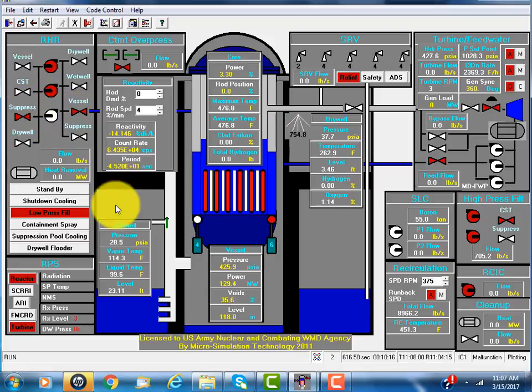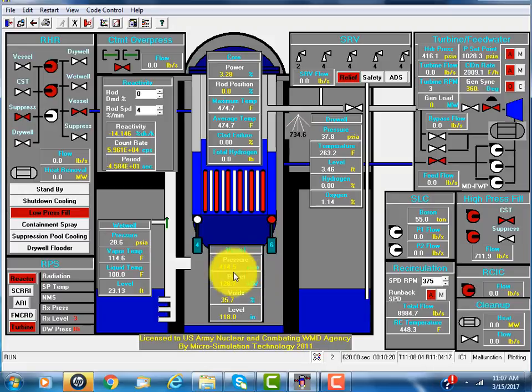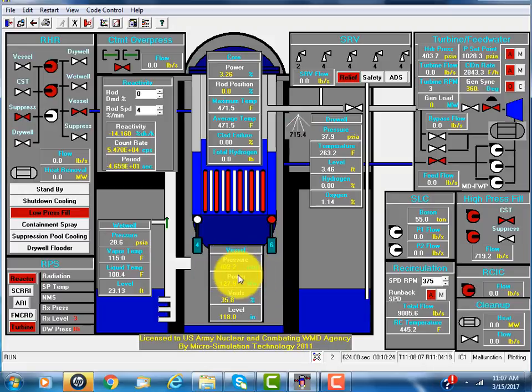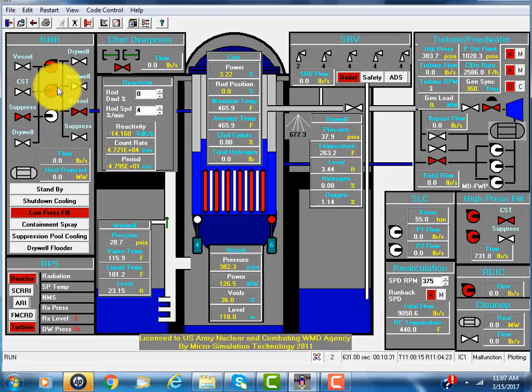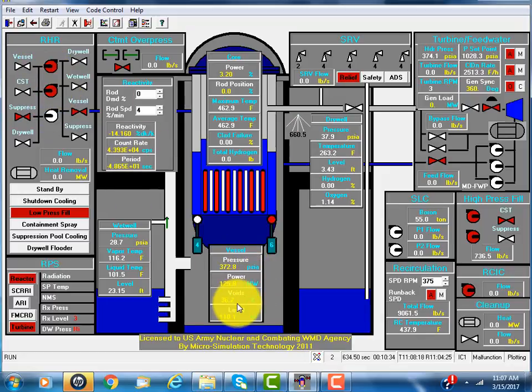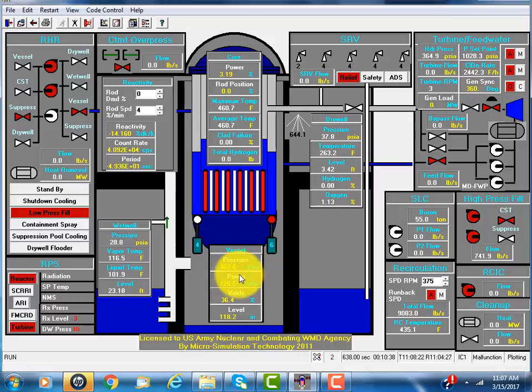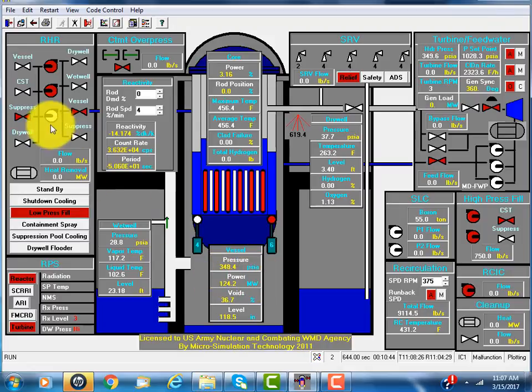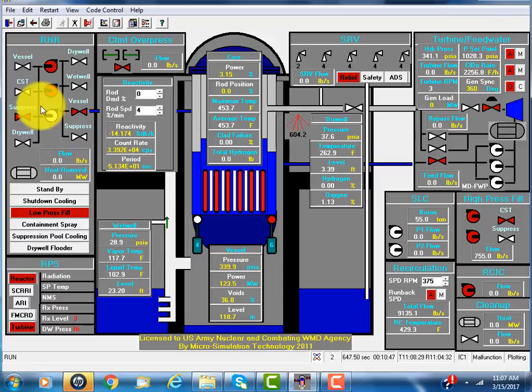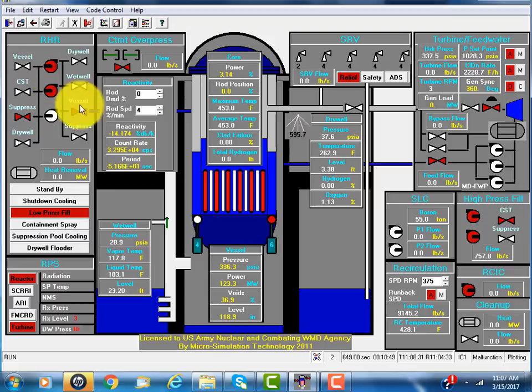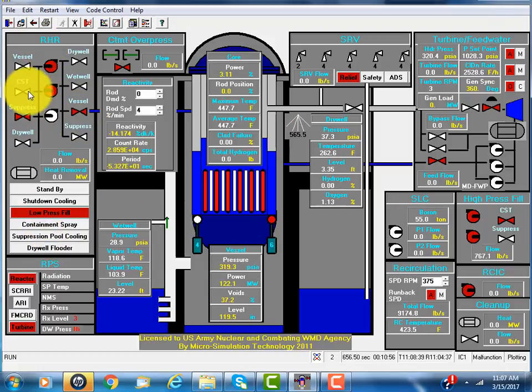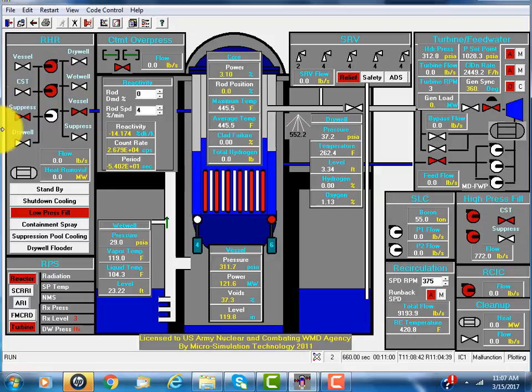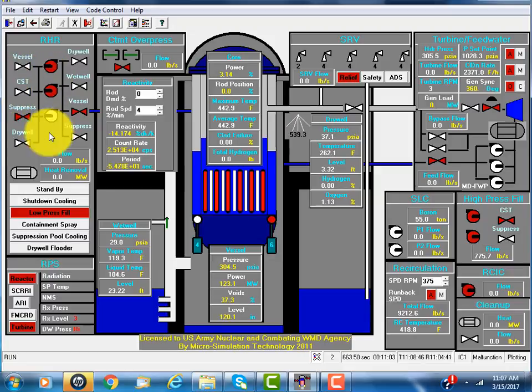Right now, the pressure is still pretty high, 400 PSI. This is a low pressure pump. They'll wait until the reactor pressure drops to somewhere around 300, 200 PSI. That's when it could overcome the pressure to fill the vessel.